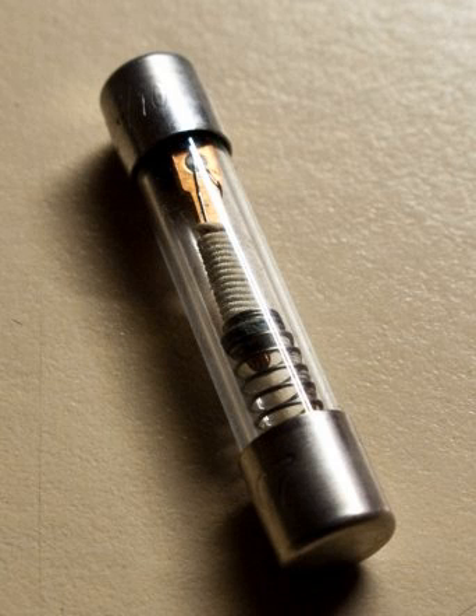Fuses only sense overcurrent, or to a degree, over temperature, and cannot usually be used independently with protective relaying to provide more advanced protective functions, for example, ground fault detection. Some manufacturers of medium voltage distribution fuses combine the overcurrent protection characteristics of the fusible element with the flexibility of relay protection by adding a pyrotechnic device to the fuse operated by external protective relays.